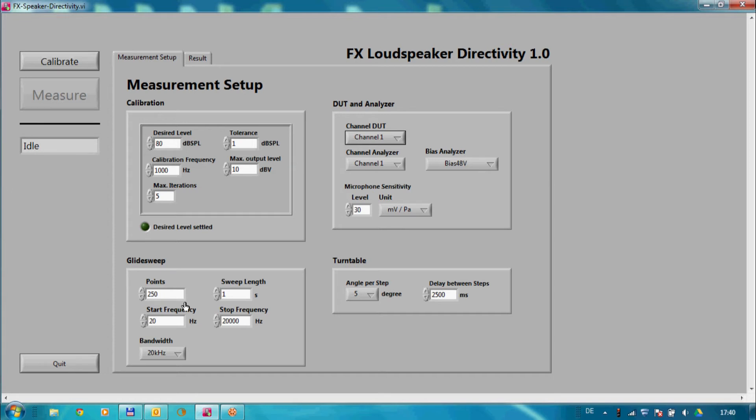On the right side, I can specify the channels for the DUT and the analyzer, and set the bias and sensitivity of the connected measurement microphone.